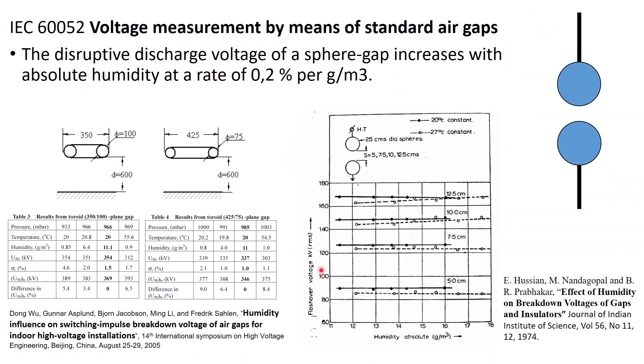Now, what is the relation between air humidity and breakdown strength of air? Here we have IEC 60052, voltage measurement by means of standard air gaps. It says that the disruptive discharge voltage of a sphere gap increases with absolute humidity at a rate of 0.2% per gram per cubic meter. So for a sphere-sphere electrode with a uniform electric field, increasing moisture increases the breakdown strength slightly — only about 2% even at 10 grams per cubic meter. In this paper for a sphere-sphere electrode, the breakdown strength is more or less constant, maybe slightly increasing.